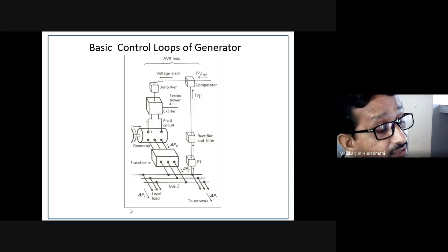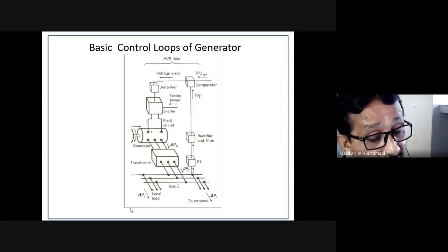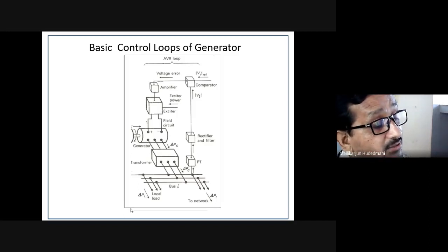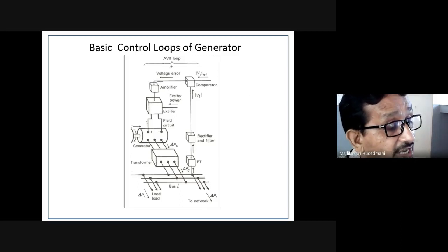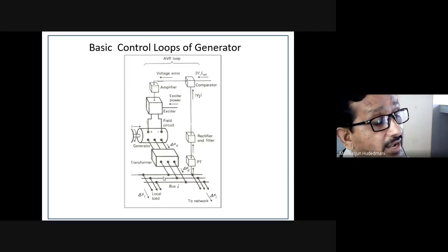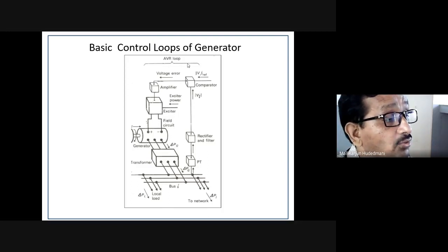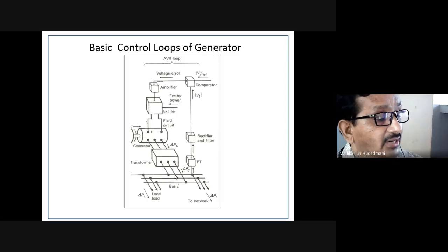This comes under AGC. AGC has to take care of managing the voltage and managing the frequency. One part we discussed, that is assigned to a generator. Managing this activity is the role of AGC. So therefore, this has to be there on each generator. I am showing you one generator. Like that, there are 10 generators. You should have 10 such setups associated with each generator acting to the requirement commonly and as per requirement. This is about AVR separately.